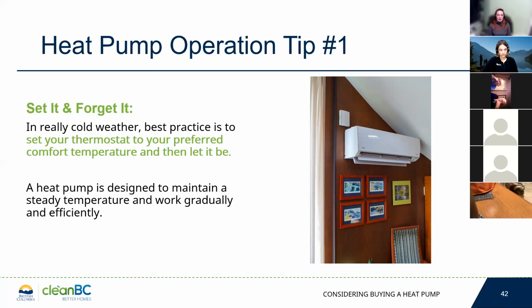Actually, the contrary is the case. A heat pump takes quite a while to get up to a certain temperature level, but once it's there, it runs very gradually and very efficiently. The refrigerant has to absorb all that heat and the compressor has to get going, so it's actually counterproductive to turn the heat pump on and off repeatedly.